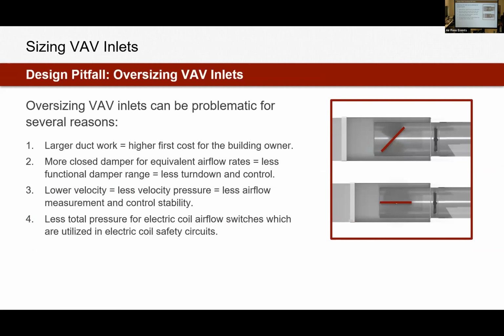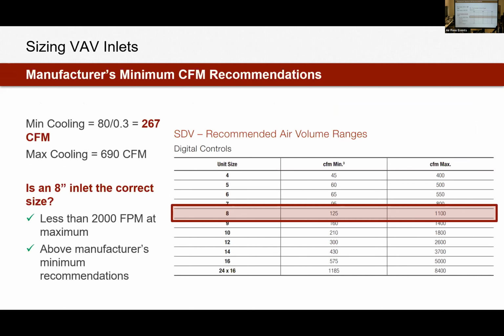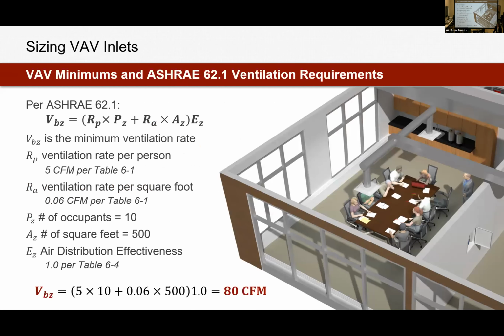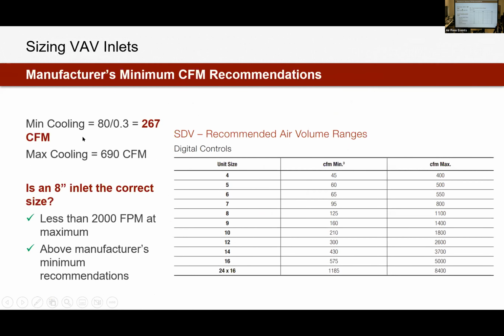Now, I have been in a number of engineers' offices where they tell me, yes. Let me go back one, or two slides, I guess. So the minimum cooling was 80 CFM. How did you get to 267 on the next slide? So this is 5 CFM per person, 10 people. That's your outside air, your ventilation rate. Okay, so then 30% of total airflow is ventilation. Oh, because you're 70-30. Okay, that's the part I was missing. Yes. I jumped slides, it was also like, wait, why did that airflow change? But I'm just going to keep rolling. I'll never notice.